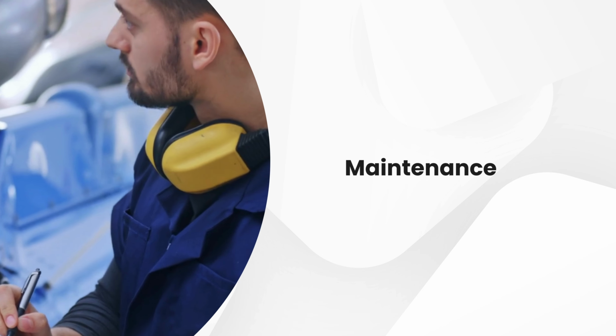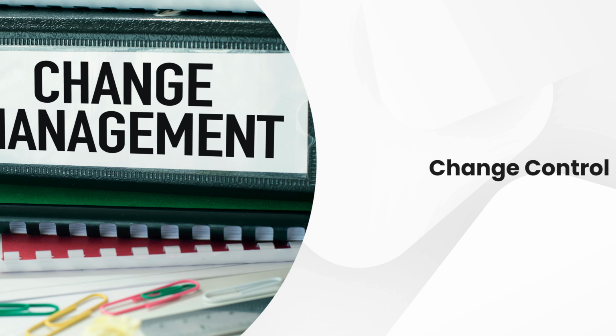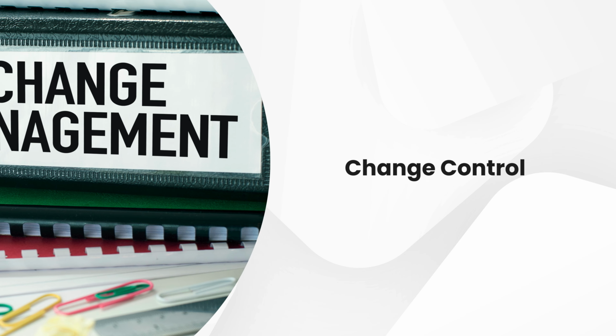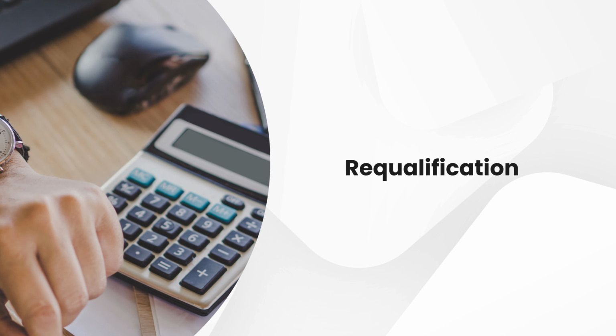Change control. Any changes to the system, software, or analytical method must be assessed for their potential impact on the qualified state. Qualification isn't a one-time event. Over time, instrument performance can drift. Requalification or periodic checks are necessary to maintain confidence in your results. The frequency depends on factors like instrument usage, the criticality of the application, and regulatory requirements.